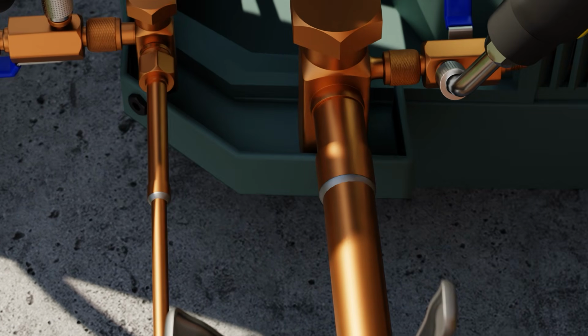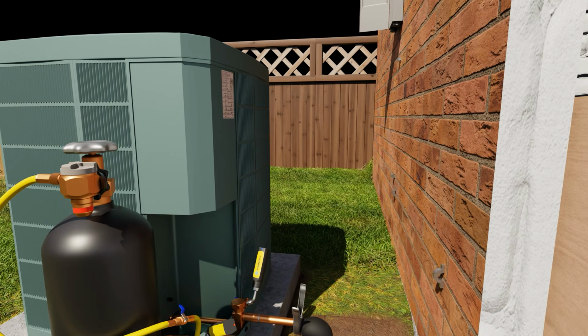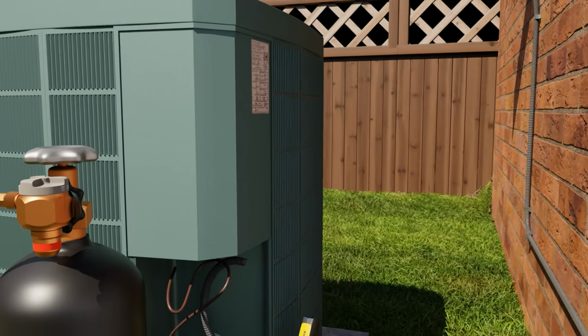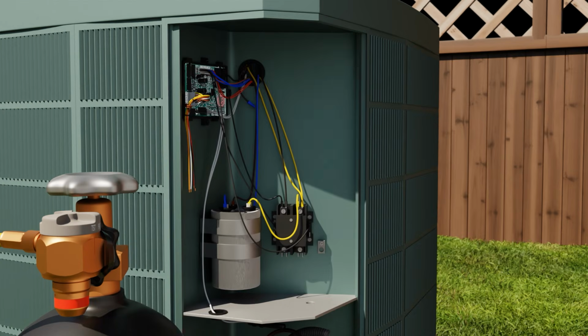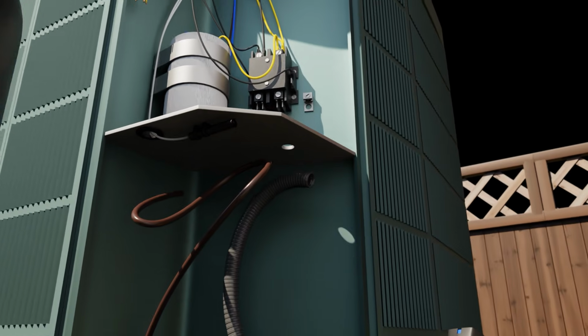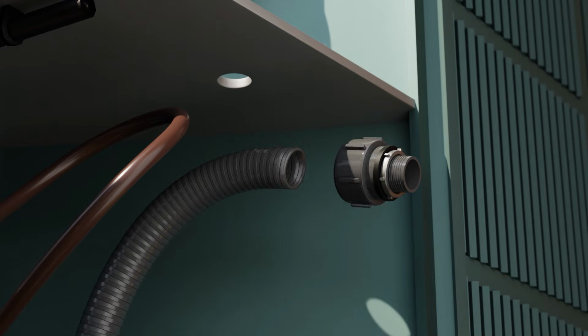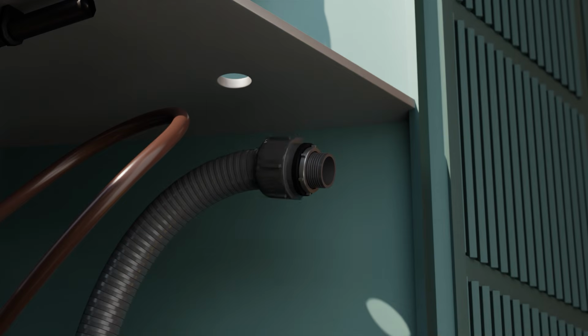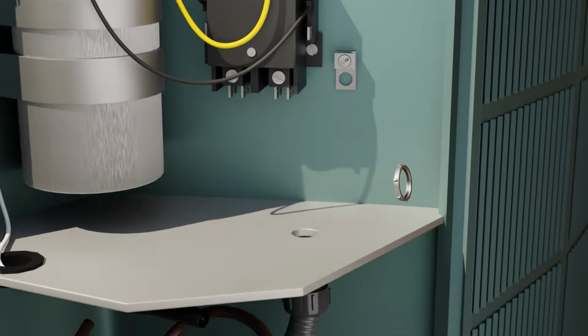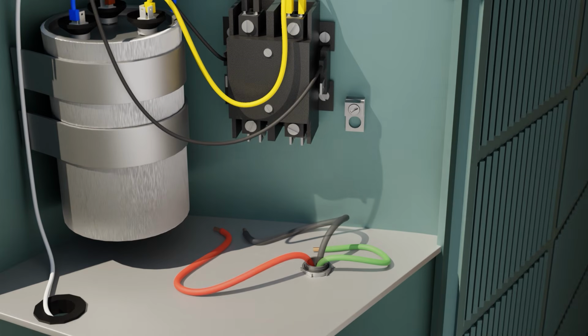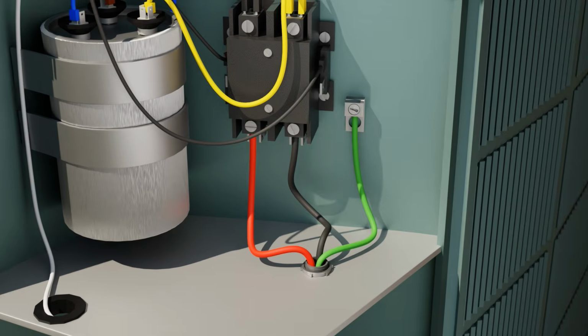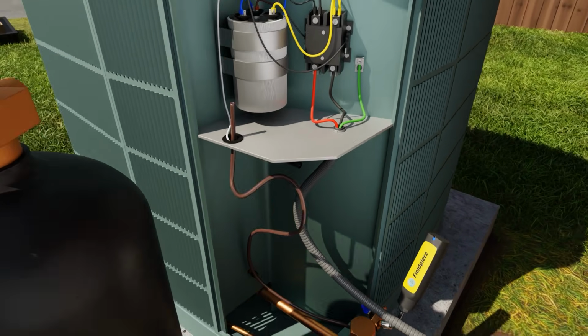The next step is showing electrical connections. You could actually have begun some of these connections while you were waiting on the pressure test. Now you can begin to make your electrical connections. Again, this doesn't need to be done before your vacuum. In most cases, you're going to begin pulling your vacuum at this point. We're just showing this part here. First, you connect your high voltage. Now you connect your low voltage.